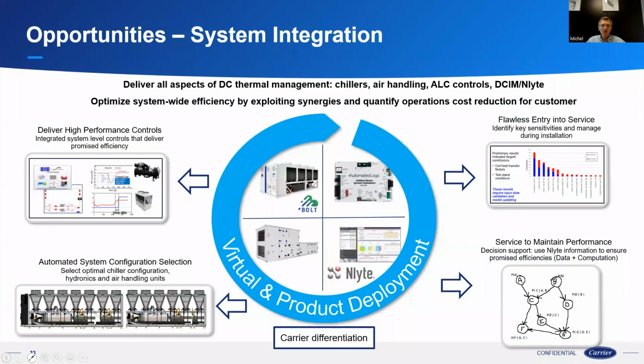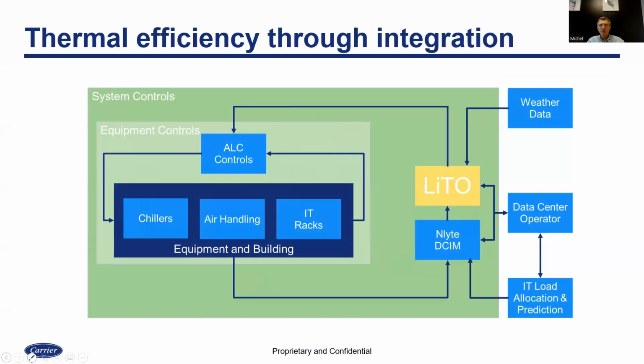My last point is that going forward, we see a lot of opportunity in connecting DCIM, which has information directly from the data center, ALC controls, and thermal systems, meaning chillers and air handling units. If we take into consideration the given load, weather data, and IT load, we can optimize all set points in the data center and actually reduce its operational cost through smart management of set points, which today is not always the case.